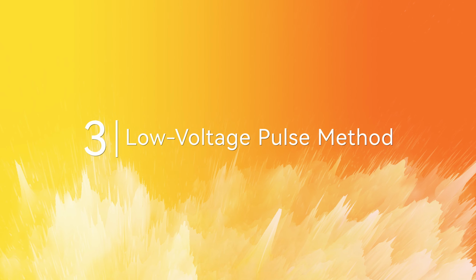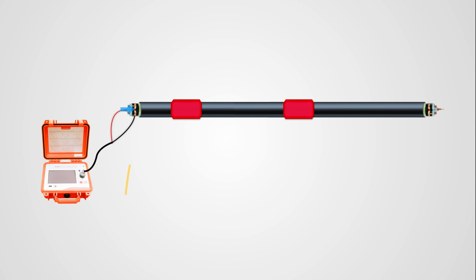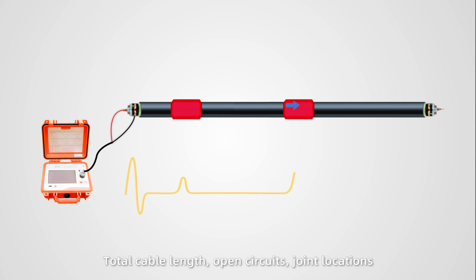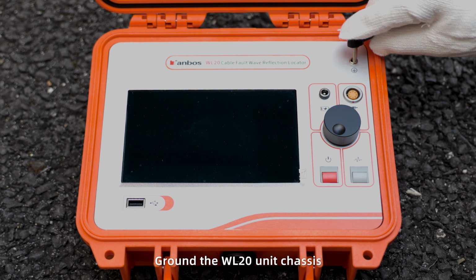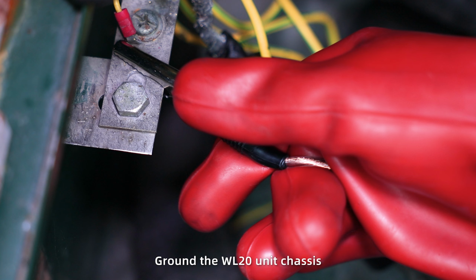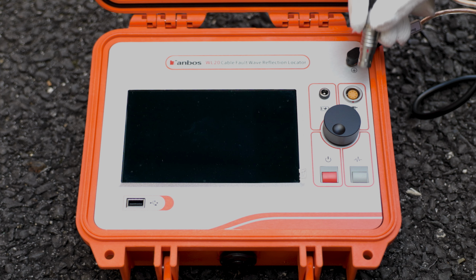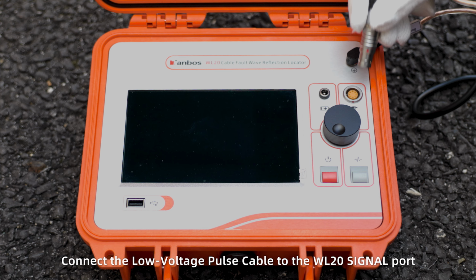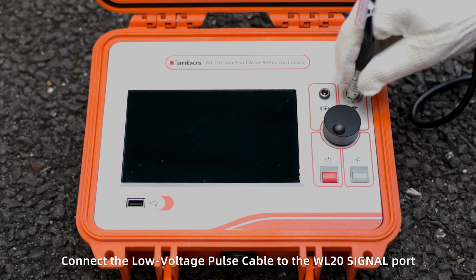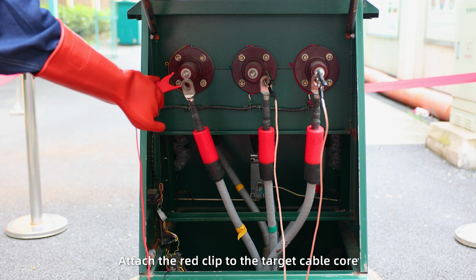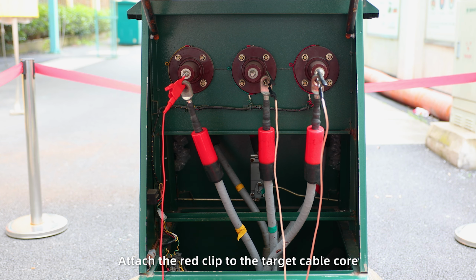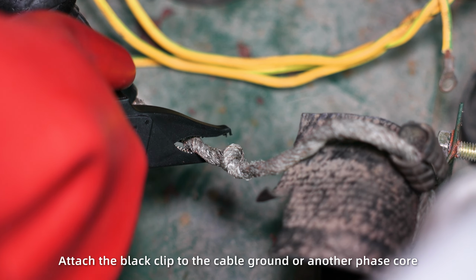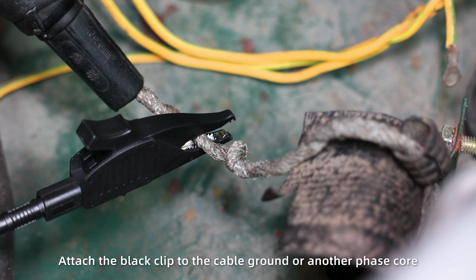3. Low voltage pulse method. Used to measure total cable length, open circuits, joint locations, and low resistance fault distances. Ground the WL20 unit chassis. Connect the low voltage pulse cable to the WL20 signal port. Attach the red clip to the target cable core. Attach the black clip to the cable ground or another phase core.